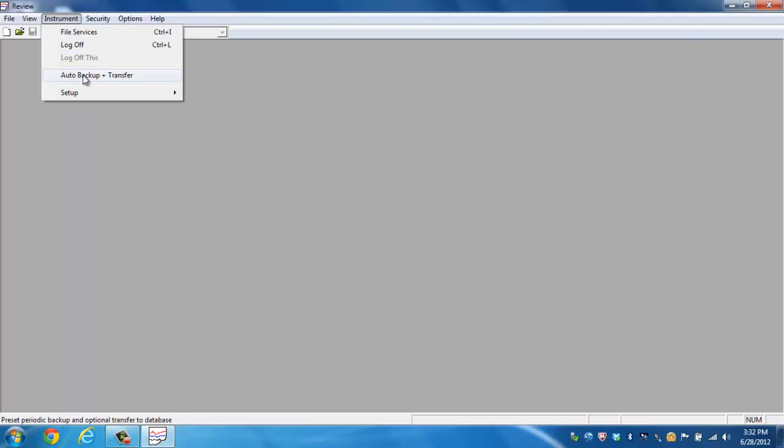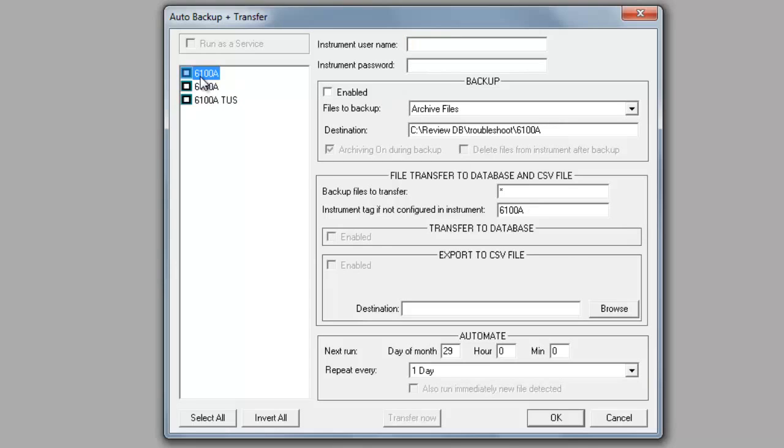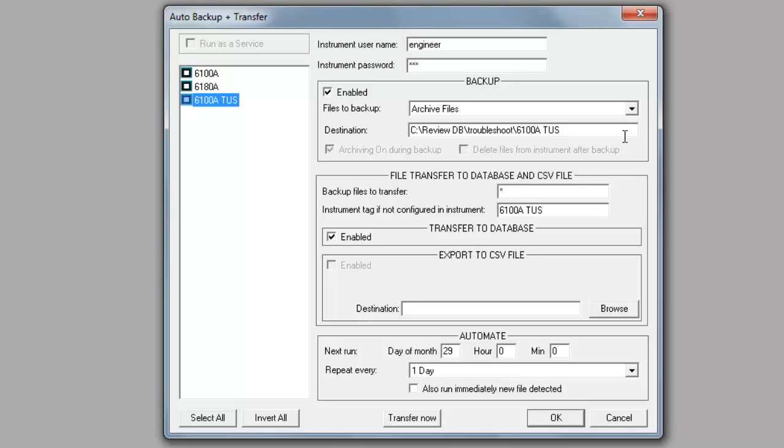Once you have that done, the next step would be going to the auto backup and transfer. What's nice about the auto backup and transfer is this serves as a two-fold function. First, you select what instrument you want to use. When you have that device selected, input the username and the password. By default, that username is going to be engineer, the password is going to be 100. Now if you change the password at a later time, that password needs to change as well. In order for this process to work, however, you do need to click on the enabled underneath the backup window here. Because the way that this works is it logs on to your recorder or nanodac, looks at any files that it doesn't currently have in its master archive folder, and backs everything up into that directory. It is taking that raw data and backing it up. So in the event that something happens to your recorder or nanodac, you at least have the raw encrypted data to recreate a chart at a later time.